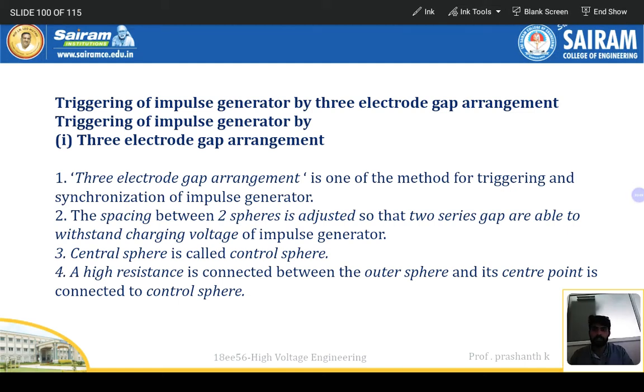Let us discuss triggering of impulse generator by 3 electrode gap arrangement. I think this is the last video of your module 2 of the high voltage engineering subject. The name itself indicates we are having a 3 electrode gap to check the impulse voltage, to check the particular specimen, particular components, flashover and impulse testing. So the 3 electrode arrangement is one of the methods for triggering and synchronizing the impulse generator.